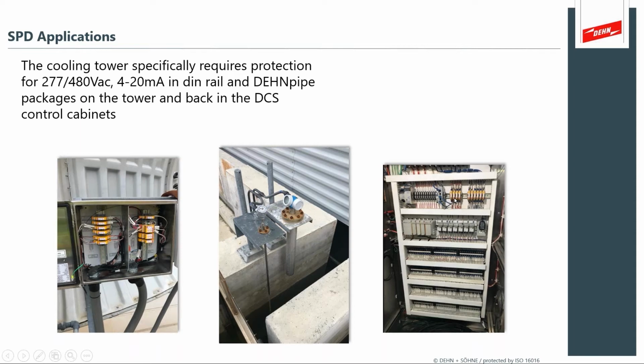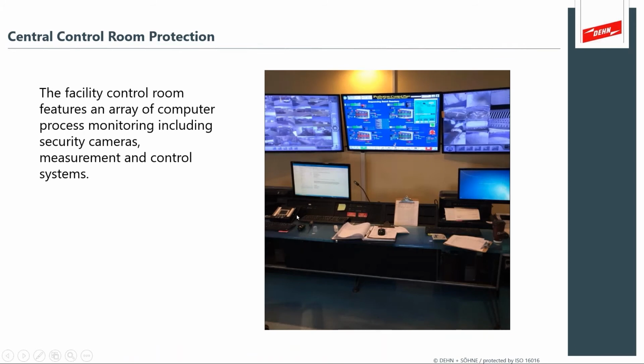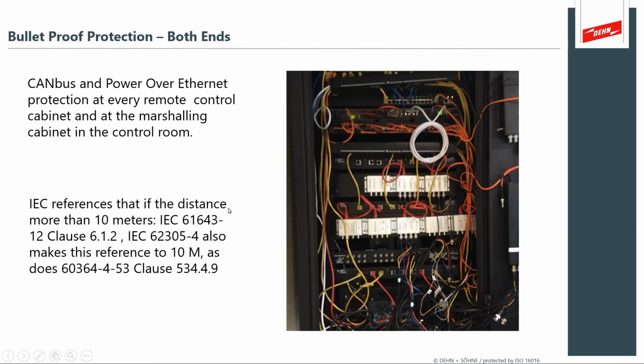We see in the standards that wire runs of anything more than 10 meters have a very strong suggestion to apply surge protection measures at both ends. This is a really good set of photographs that show you how to apply surge protection both at the sensitive victim, right at the point of use, and then back at the DCS control cabinets. Of course, you have all of the processes being controlled at the central control rooms. These are all very delicate, low voltage control systems that have to have surge protection measures applied. You have bulletproof protection at both ends.